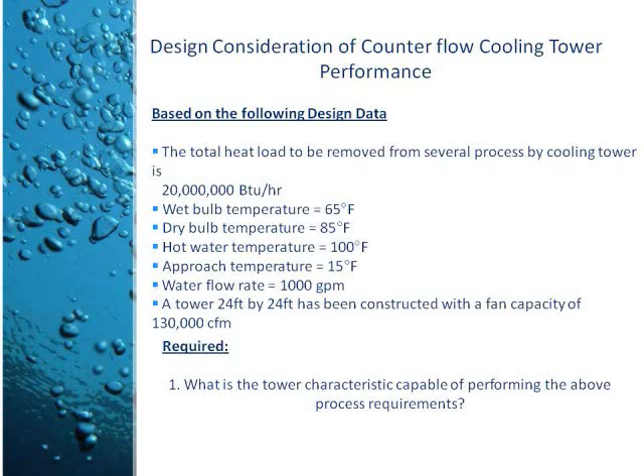The approach is 15 degrees Fahrenheit. From here, we can get our cold water temperature by adding the approach to the wet bulb temperature of 65 degrees Fahrenheit. Thus, our cold water temperature is equal to 80 degrees Fahrenheit. We are also given a water flow rate of 1,000 gallons per minute. The dimensions of the tower are 24 feet by 24 feet, and it has a fan capacity of 130,000 cubic feet per minute. We are required to get the tower characteristic capable of performing the above process requirements.